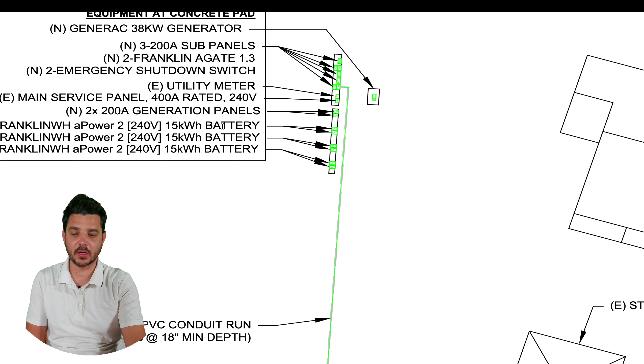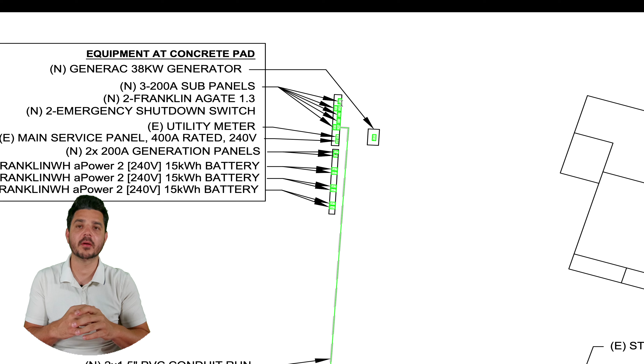And this is where that error was. It's 30 kilowatts, not 38, on the generator. It backfeeds 150 amps. So that's going to go into a generator sub panel, and then it gets split into 2 100 amp breakers, one for each aGate, using the generator auxiliary adapter. So both systems will be able to charge and power the home from the generator. It's sufficiently sized for it, and there shouldn't be any issues in that regard.